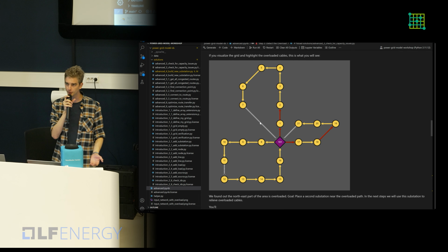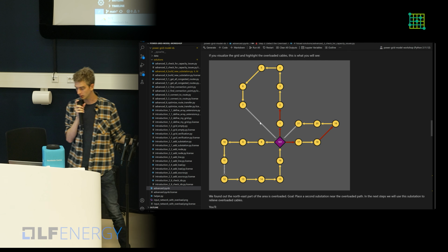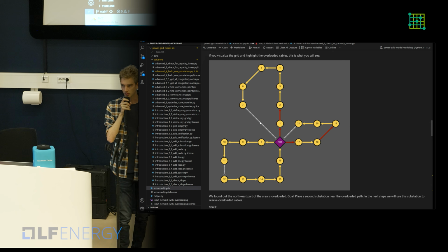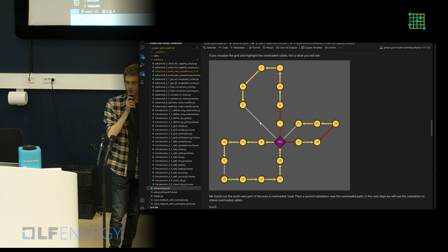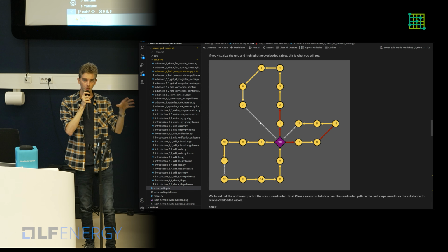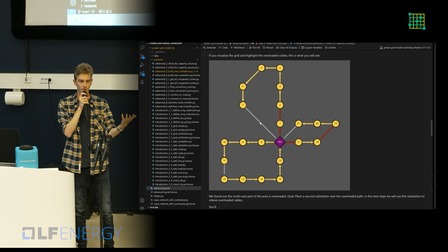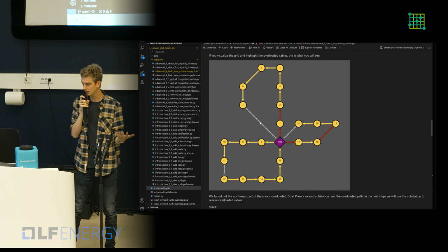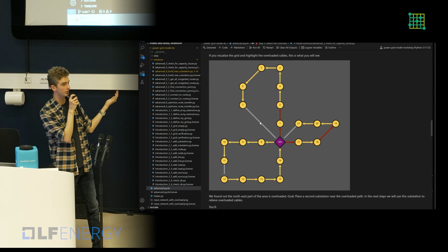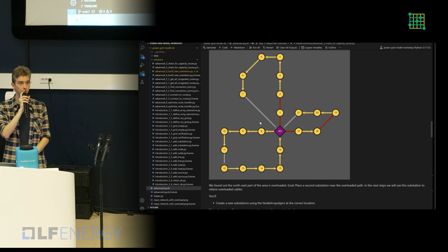So there's, of course, multiple ways to solve this. We can upgrade the capacity of our cable by putting a new cable into the ground. But another way to do this is to place a new substation. So we currently have 1 substation in the center of our grid. And we can place a new substation, connect some of the nodes using a new cable to our new substation, and then supply the required power, the required load, partly through that new substation. And that should relieve our currently overloaded cables. It is, and this is what we're going to do. But we want to do it data-driven.